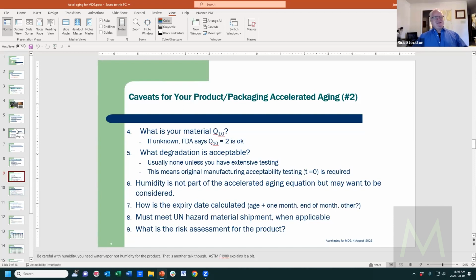Well, I know when I was working with pacemakers and I found out how fast batteries discharge with high temperatures, I got a little concerned. Then I found out my package actually started melting before it hit the temperature that affected the product. So I could say if my packages looked melted, or we had a double barrier and it's stuck together, don't use the product, period. And that worked out really good. So we had temperature control through the packaging.